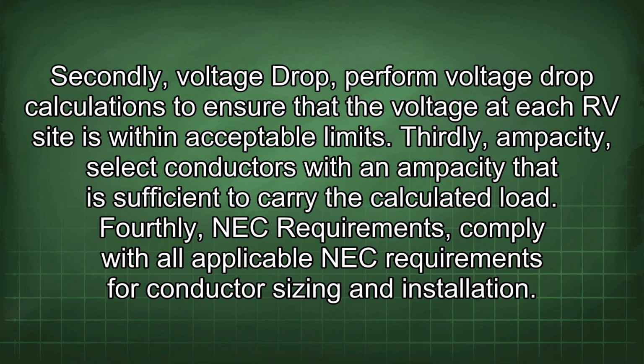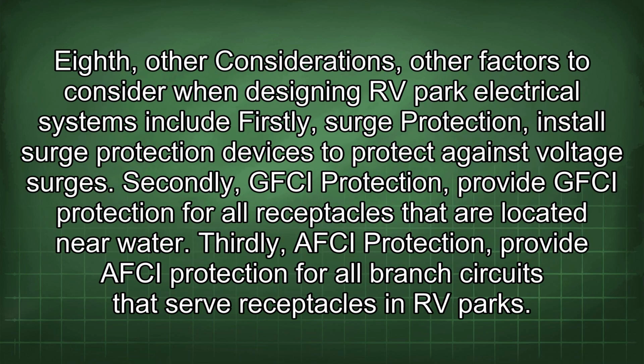Thirdly, ampacity. Select conductors with an ampacity that is sufficient to carry the calculated load. Fourthly, NEC requirements. Comply with all applicable NEC requirements for conductor sizing and installation. Eighth, other considerations. Other factors to consider when designing RV park electrical systems include: firstly, surge protection. Install surge protection devices to protect against voltage surges. Secondly, GFCI protection. Provide GFCI protection for all receptacles that are located near water.